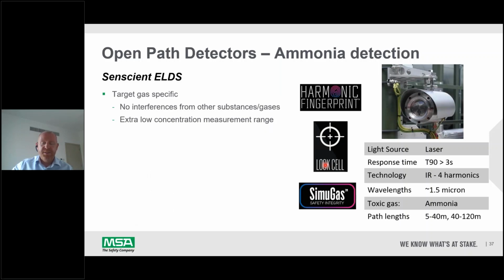So they protect boundaries of large ammonia plants, and they could be used for large cold stores for ammonia detection in food processing areas if required. One system can detect 50 meters, but for point detectors, you may need 10 or 15 point detectors and 10 or 15 sensors. So they have huge benefits over point detectors, but you always need to have different kinds of detection in one system.